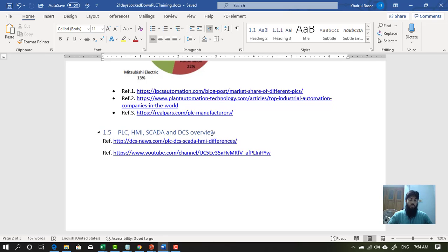Whereas SCADA is located in a control station or operator station, far away from the PLC panel. DCS as well includes the SCADA, located in a control room far away from the control panel. In some cases there may be a control panel behind the SCADA system, but the point is it can be located far away, to cover the whole plant, which may be as huge as a few square kilometers in a DCS system.